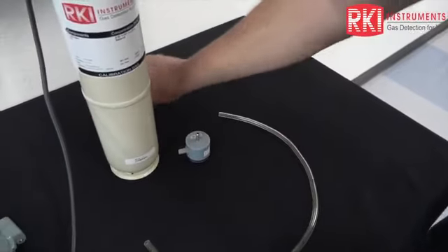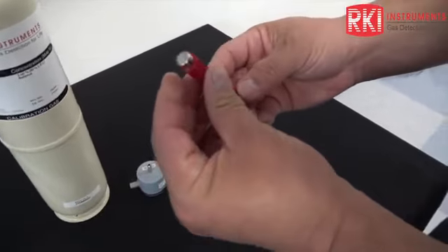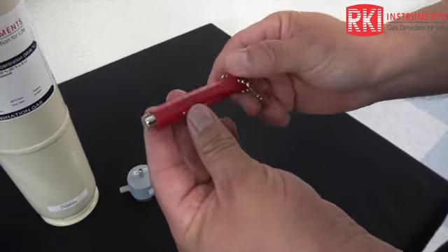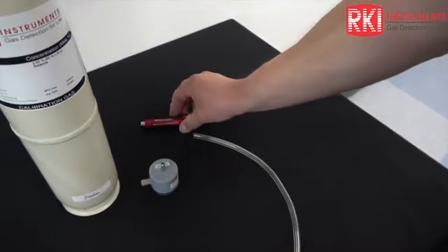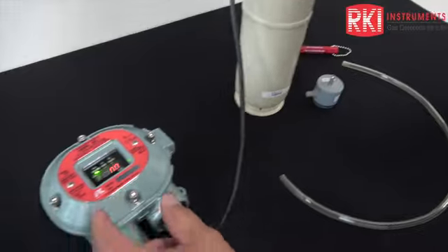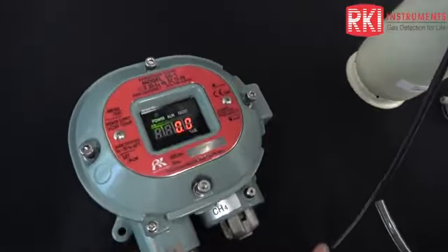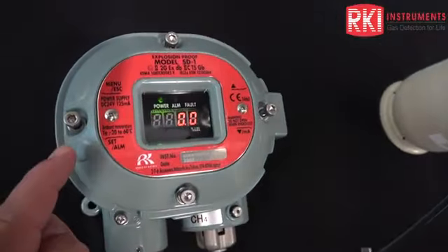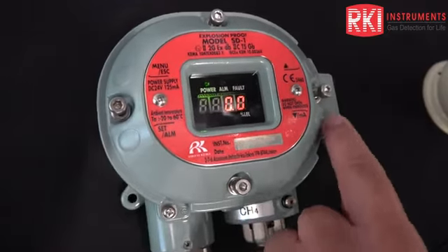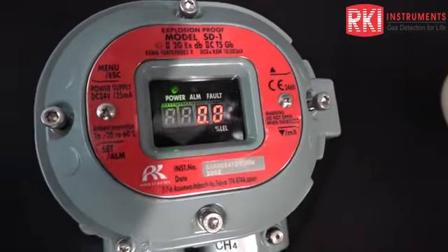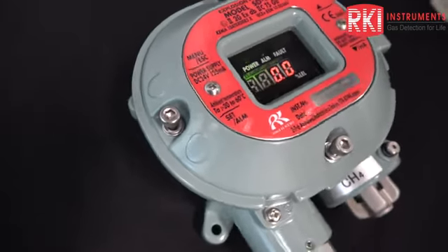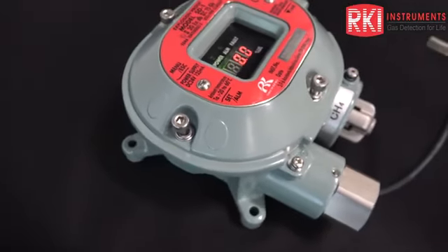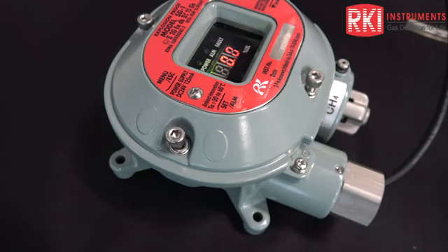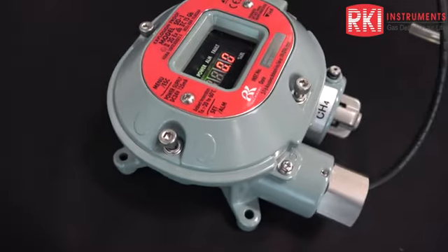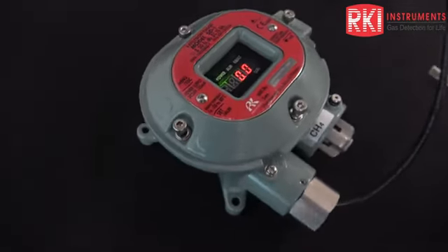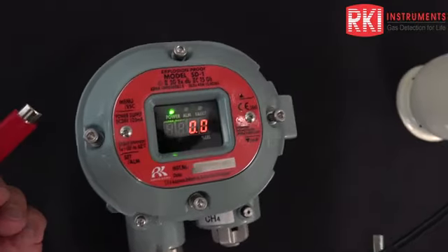All right, and then we also have a magnet. So this is a magnet that we can use for non-intrusive calibration. Since the detector head is explosion proof, once you have these screws tightened down, then you can use the magnet to touch these little pads that are on each side of the housing to access different modes. All right, so we'll do that right now. I've already got the regulator on the cylinder. So I'm going to take my magnet and I'm going to hold it up to this top pad here.